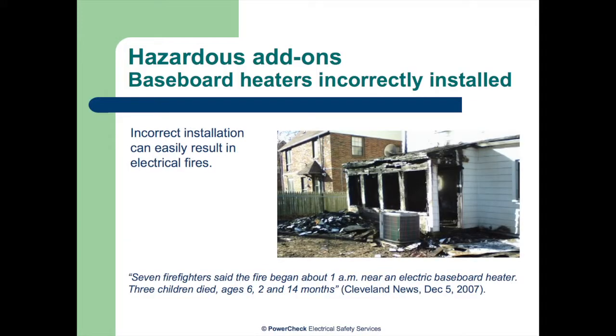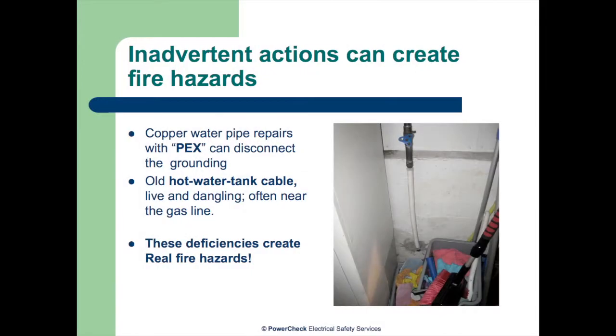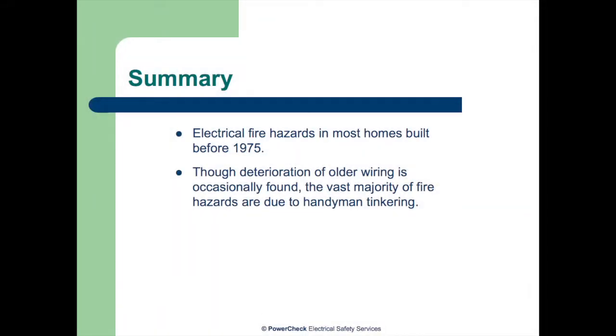Baseboard heaters incorrectly installed. A new problem we're seeing all the time now is PEX pipe repairs. People fixing a little bit of the copper system with plastic pipe. Well, what that does is it chops your grounding, because copper water pipe system is part of the grounding system in these older houses. Summary: electrical fire hazards in most houses built before 1975 are found. Though deterioration of older wiring is occasionally found, the vast majority of fire hazards are due to handyman tinkering.